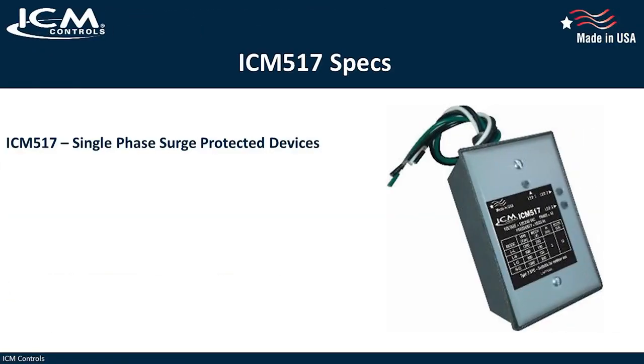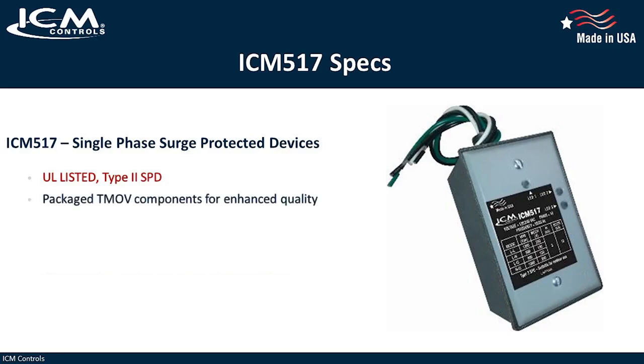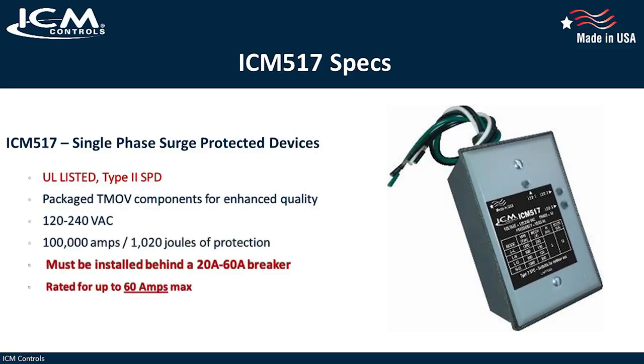The ICM 517 is UL listed as a Type 2 device and is protected by banks of TMOVs. The TMOVs that ICM uses are packaged components that are machine inserted with precision, further improving the quality of the product. The unit is rated for both 120 and 240 VAC, provides 100,000 amps of protection, and is backed by a limited lifetime protection warranty. And because this device is a Type 2 device, it means the HVAC contractor can install it, but it has to be installed behind a 20 to 60 amp breaker.